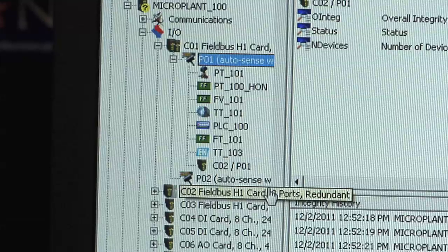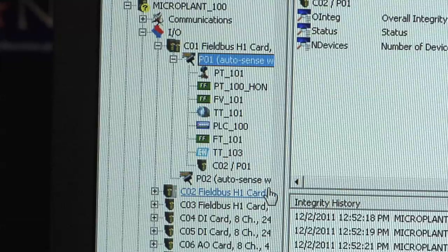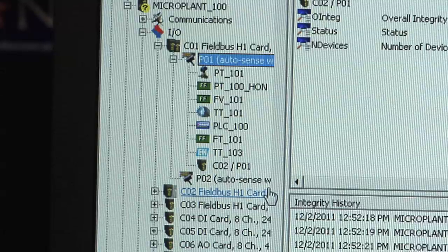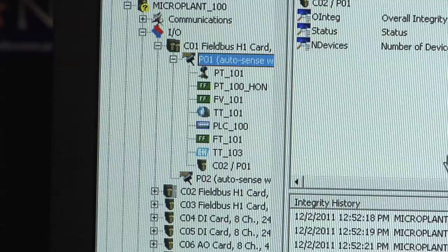Well, here the issue is yet another one. So I've actually thrown 2 curveballs in here. This is an issue where if the device had come from another host system that perhaps had a broader address range capability, it could have an address that was misset that is outside of the range of this host. Those are known as the first unpolled node and the number of unpolled node settings. So that's one possibility.